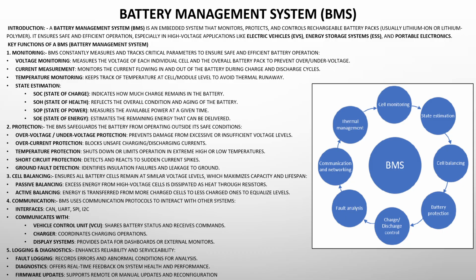First is monitoring. It's constantly measuring everything: voltage, not just the whole pack but each individual cell, current flowing in and out, and temperature, often in multiple spots because heat is the enemy. Avoiding thermal runaway is priority number one, can't have fires. It's also continuously estimating states like SOC, SOH, SOP, and SOE, state of energy or remaining energy.